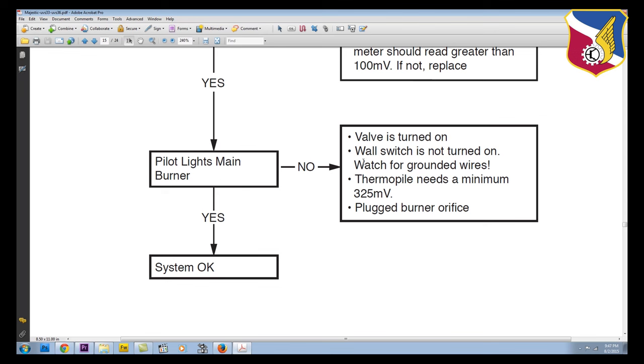Now if the pilot light does stay lit, then does the burner come on? Now if the burner doesn't come on, again go back to the thermopile, it again needs 325 millivolts. Is the valve turned on? Is the wall switch on or off? You need to make sure that those are the conditions. Do you have a plugged orifice? And if all these check out, the system should work.